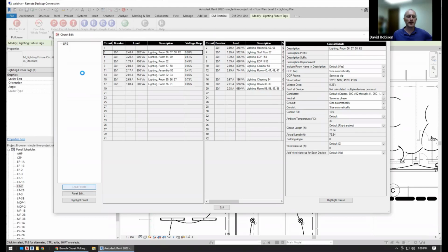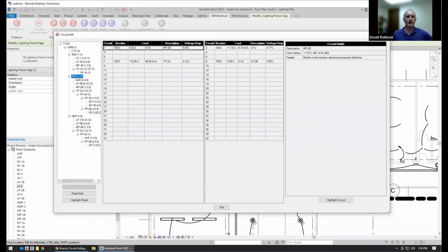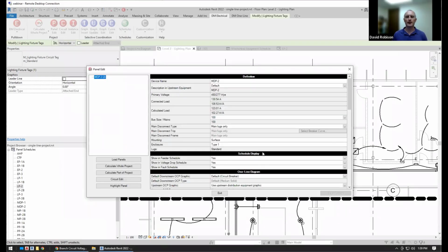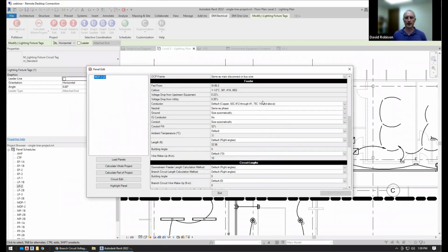If we take a look at a panel that has panels below it, so say we take this MDP2, we select this circuit that's connected to MP2B. For the circuit details, it shows you the wire size, and then it says, if you want to make any changes, go make those changes in the panel itself. So when we're looking at circuit details, those are really for branch circuit settings. For feeder settings where you're connected to another piece of equipment, you run panel edit, and you go make the changes here in the feeder section. So if you wanted to change how that panel was being fed, you change it here.